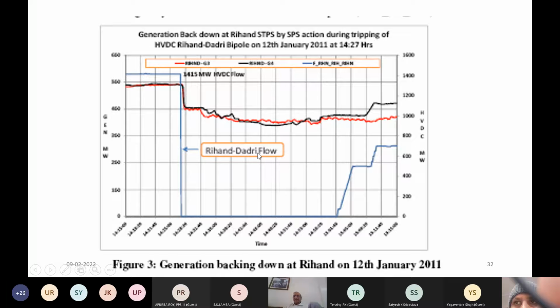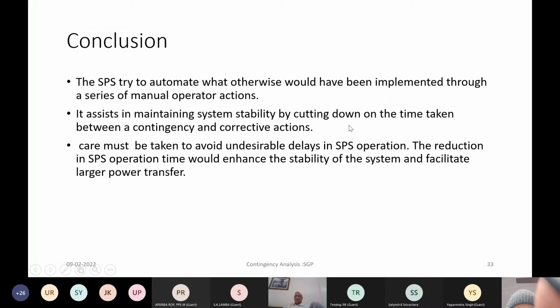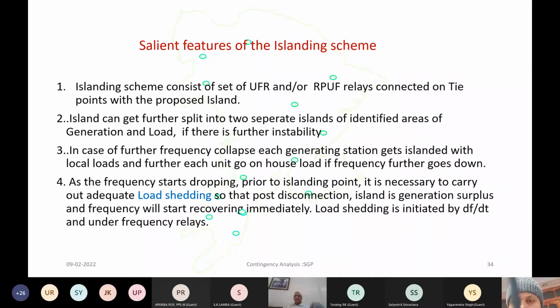You can see on the Rihand Dadri corridor the power flow from this level has come down to 0 because of the tripping of this bipole, and again the generation was then reduced automatically to keep the line loadings under control. Yeah, so this is what a special protection scheme does.